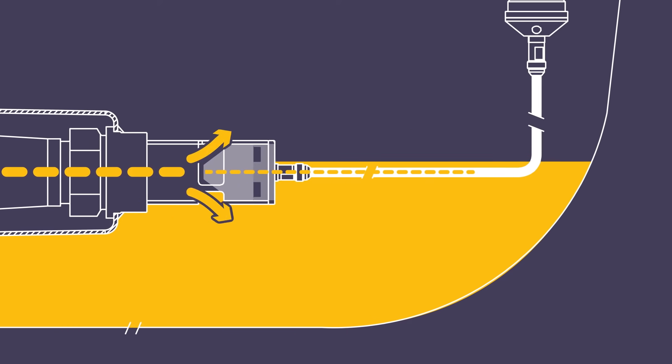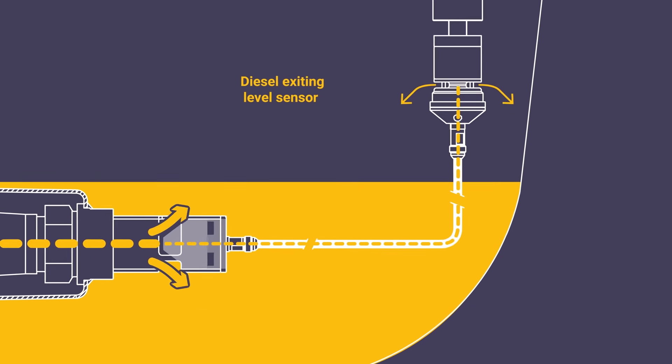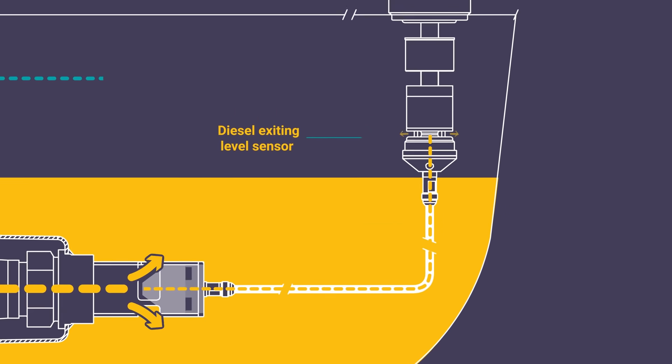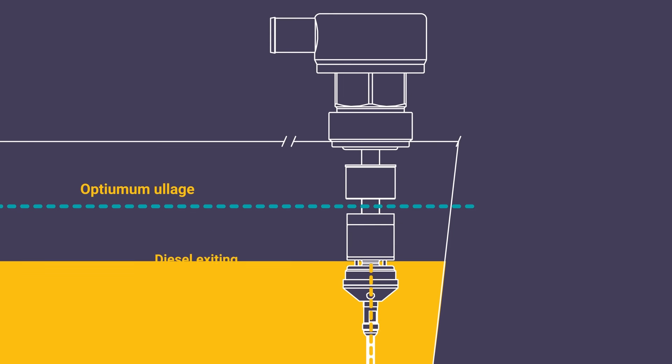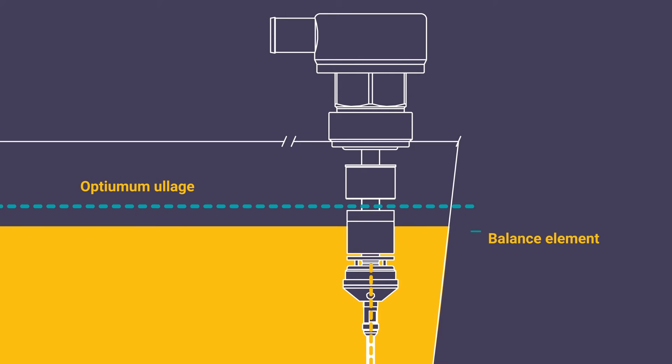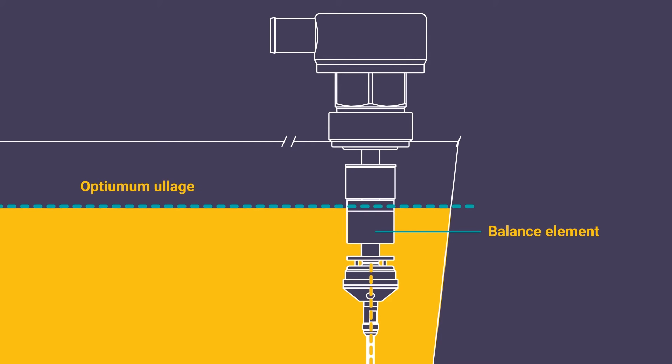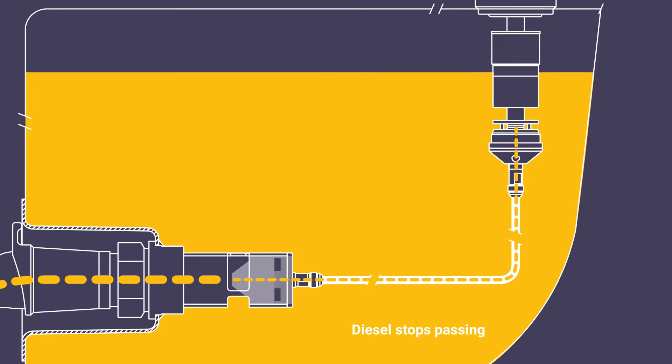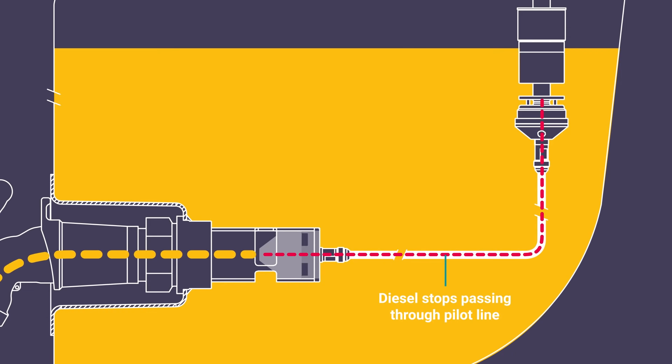A trickle of diesel travels from the flow control valve through the pilot line and out of the bottom of the level sensor. When diesel within the tank reaches the optimum ullage, it interacts with a balanced element in the flow control valve which stops the trickle of diesel passing through the pilot line.